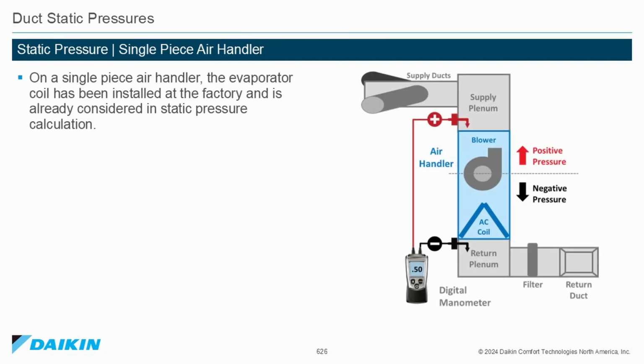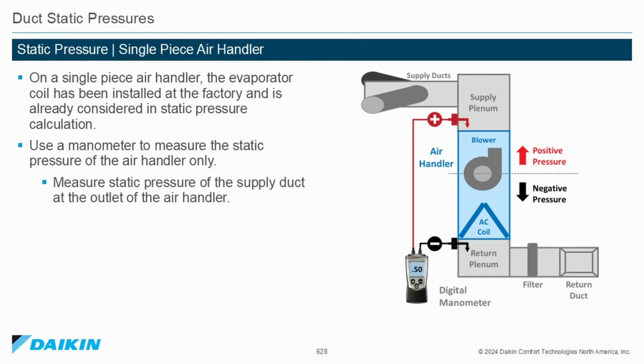Static pressure on a single-piece air handler. On a single-piece air handler, the evaporator coil is installed at the factory and is already considered in the static pressure calculation. Use a manometer to measure the static pressure for the air handler only. Measure static pressure of the supply duct at the outlet of the air handler. Measure the static pressure of the return duct at the inlet of the air handler.